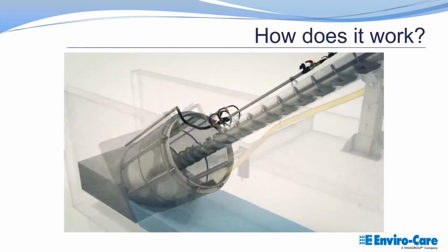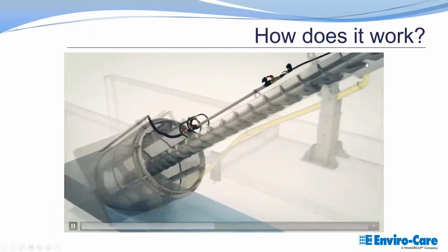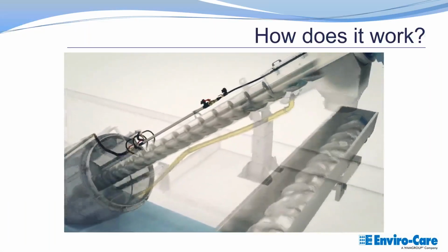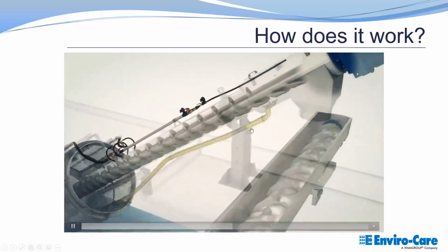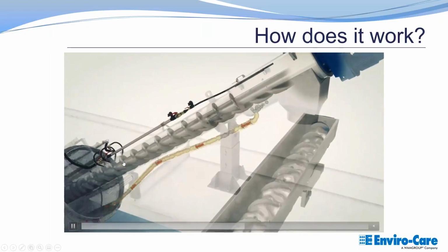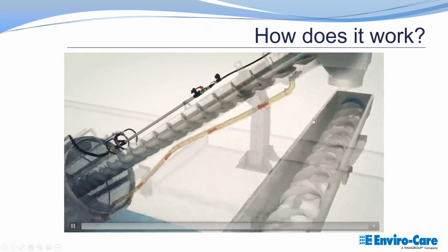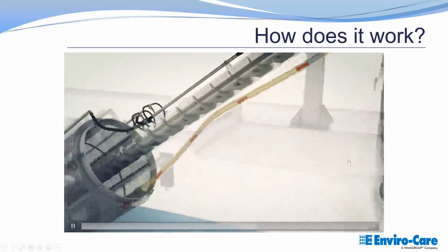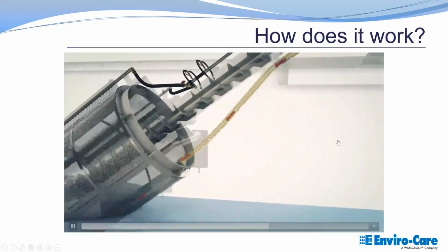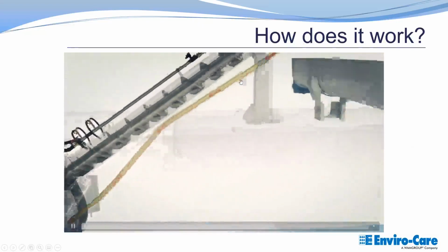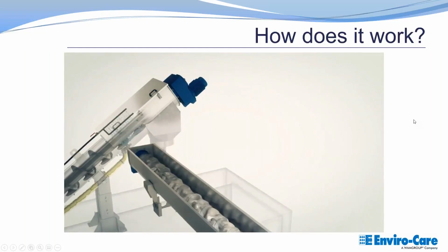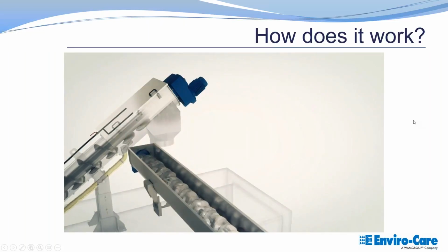And at the very top, there will be a compaction zone that's taking all that captured material, squeezing it, additional cleaning going on, and then taking all the water that's cleaned out of it and bringing it back down into the channel so that you've got only the dry material coming out. And that can go either straight into a dumpster or that can go into a conveyor system as they show here. It's a very simple unit, and one of the main benefits being everything is integral to the unit, including the compaction zone. So it makes it much more cost effective, especially for smaller plants.